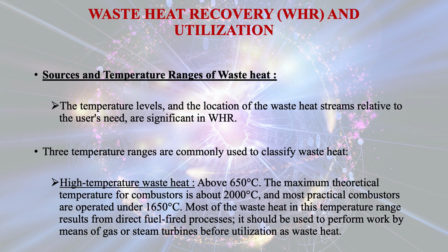Three temperature regions are commonly used to classify waste heat. High temperature waste heat is above 650 degrees centigrade. The maximum theoretical temperature for combustion is about 2000 degrees centigrade and most practical combustors are operated under 1650 degrees centigrade. Most of the waste heat in this temperature range results from direct fuel fired process. It should be used to perform work by means of gas or steam turbines before utilization as waste heat.